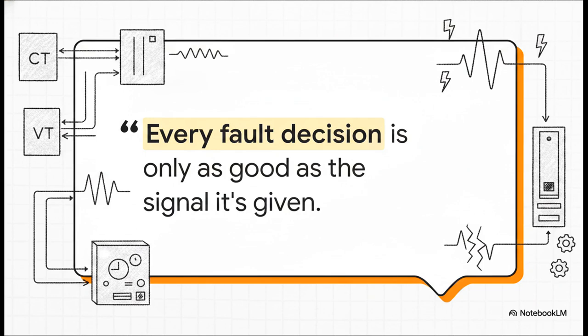Every fault decision the REF615 ever makes is only as good as the signal it's given. It's really that simple. If you get the current and voltage transformer sizing wrong, well, the smartest protection algorithm in the world is suddenly just reading a totally distorted picture of reality. The relay can literally only protect what it can accurately measure.